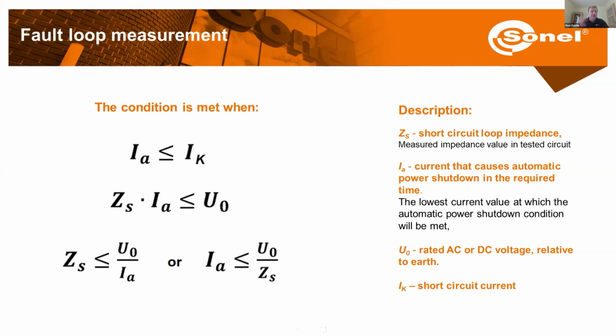Well, measuring this leakage current or the fault current itself would be very complicated. So that's why the meters measure fault loop impedance. And further, as we know the value of the impedance and the value of the supply voltage, this is going to be our fault current. And then we compare it with the specs of our breaker. If this fault current is higher than the current triggering the breaker, then the whole situation is correct.